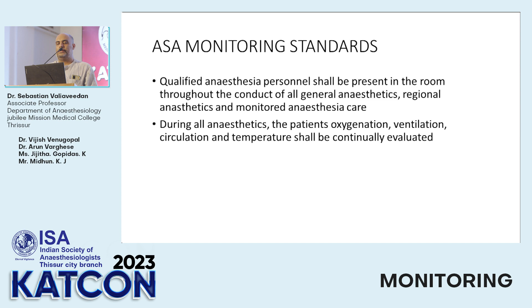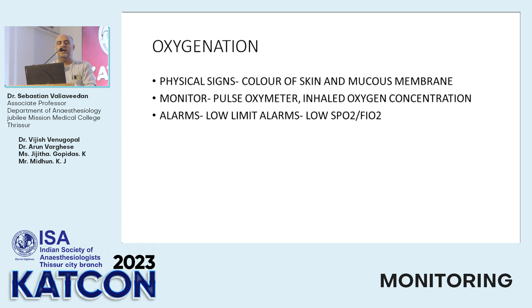So, looking back, the oxygenation, the physical signs which we look for are color of skin and mucous membrane. That is generally what is the easiest thing to do. But it has obviously got its limitations and pitfalls, the lighting, what skin you are looking at, the color of the skin, all these can always cause a lot of subjectiveness in the interpretation. So the monitors which we rely on for oxygenation are, in the blood it's the pulse oximeter, and the circuit is the inhaled oxygen concentration. And the alarms generally will alert you towards low SpO2 or FiO2 alarms, low oxygen concentration alarms.